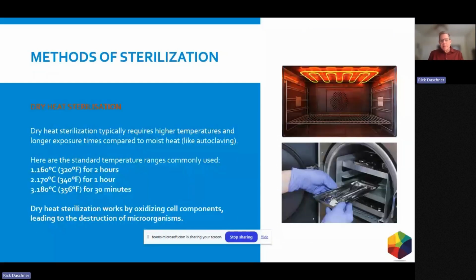Dry heat, just like it sounds. Dry heat typically requires high temperatures and much longer exposure times compared to moist heat, like autoclaving. And just to give you an idea of the differences, you're talking minutes versus hours when comparing it to steam. But standard temperatures are 160 C, 170 C, and 180 C. Now, dry heat works by oxidizing cell components, leading to the destruction of microorganisms. And you can kind of see the pictures off to the side. It kind of looks like an oven in some cases. That's a pretty rudimentary dry heat unit. And then with other dry heat units, you're not going to see the elements. And those are the more popular ones below for instrumentation.